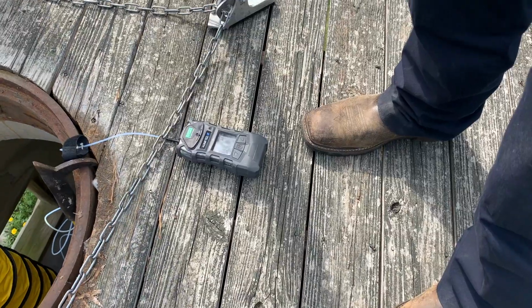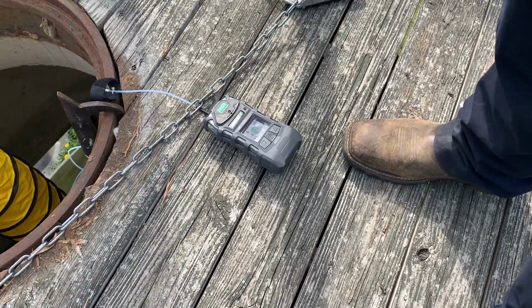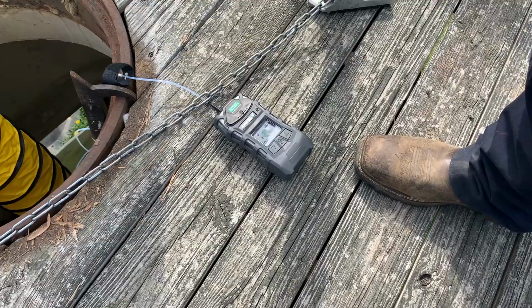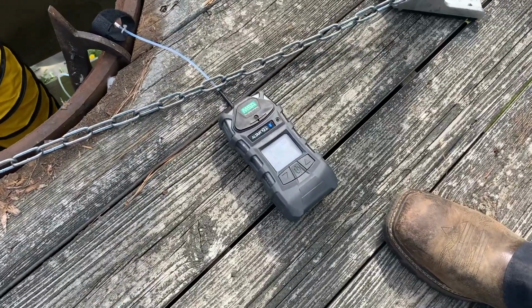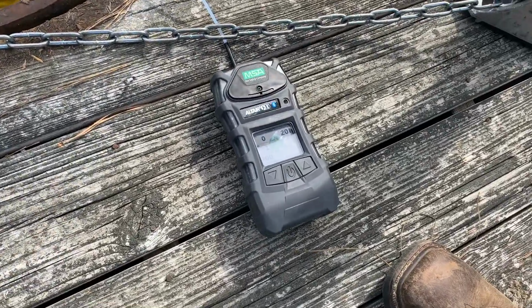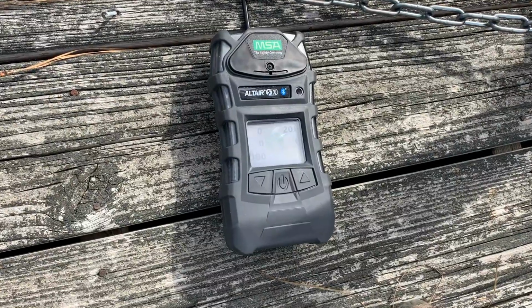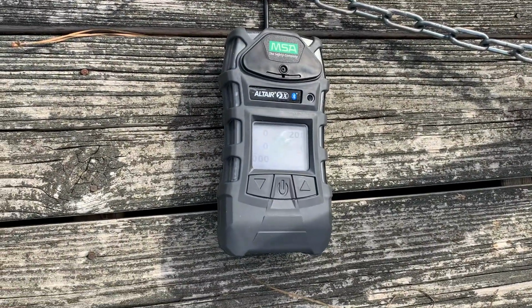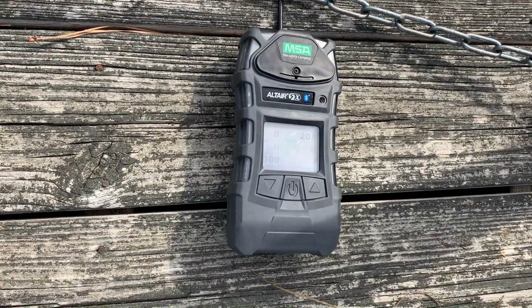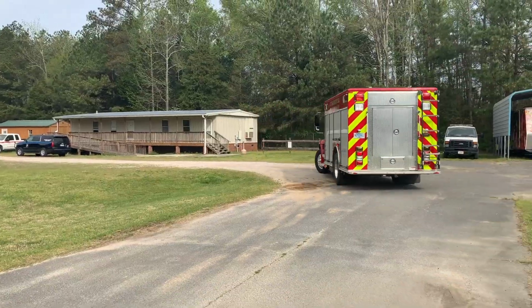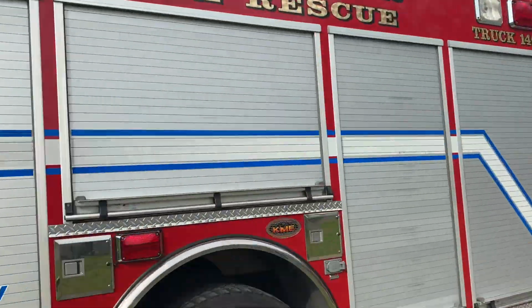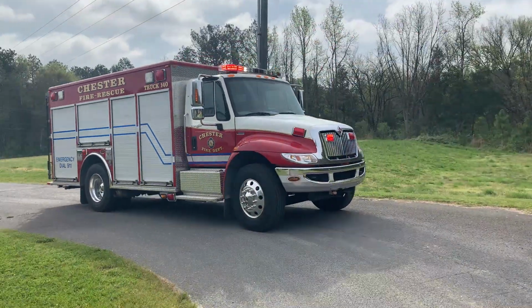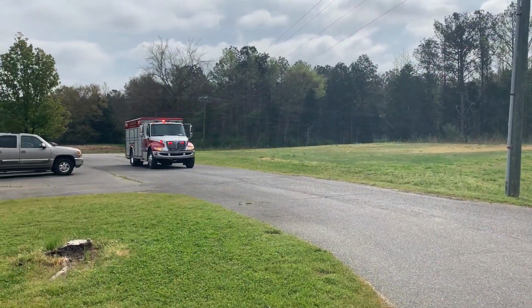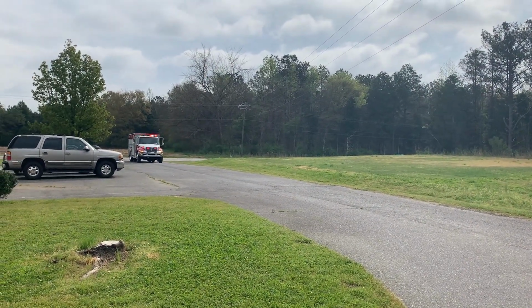The detector has 4 gas detection, including oxygen, carbon monoxide, hydrogen sulfide and methane. It is equipped with a catalytic combustible sensor that detects various combustible gases, up to 100% lower explosive limit, or LEL. If the unit alarms for combustible gases, leave the area immediately. Remaining in the area under such circumstances can cause serious personal injury or death.